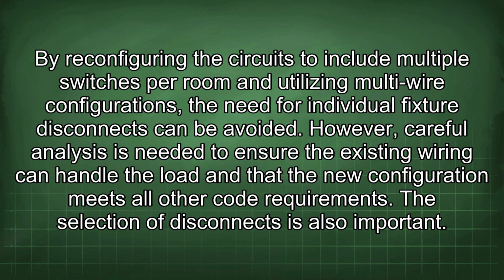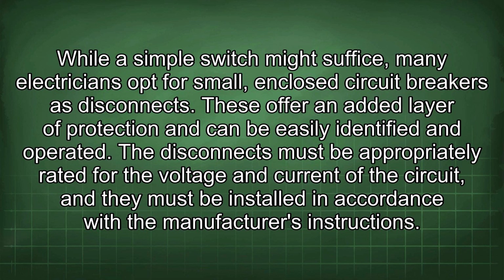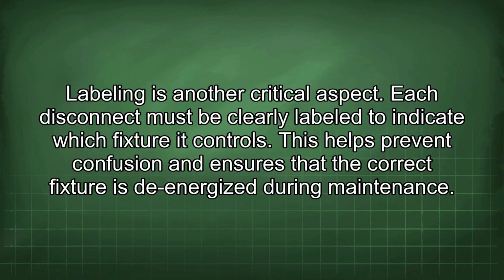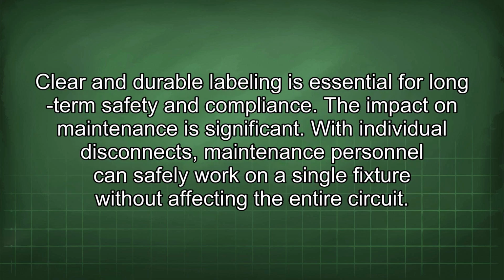The selection of disconnects is also important. While a simple switch might suffice, many electricians opt for small, enclosed circuit breakers as disconnects. These offer an added layer of protection and can be easily identified and operated. The disconnects must be appropriately rated for the voltage and current of the circuit, and they must be installed in accordance with the manufacturer's instructions. Labeling is another critical aspect. Each disconnect must be clearly labeled to indicate which fixture it controls. This helps prevent confusion and ensures that the correct fixture is de-energized during maintenance. Clear and durable labeling is essential for long-term safety and compliance.